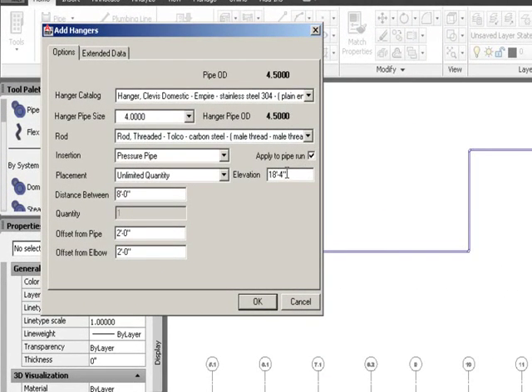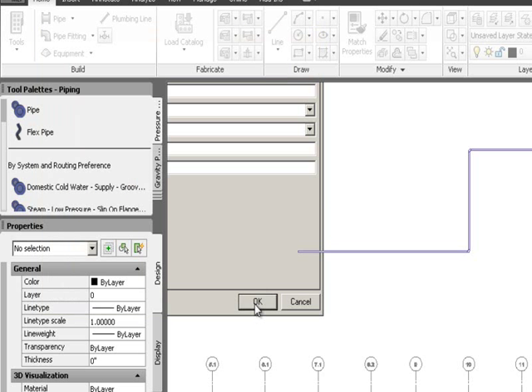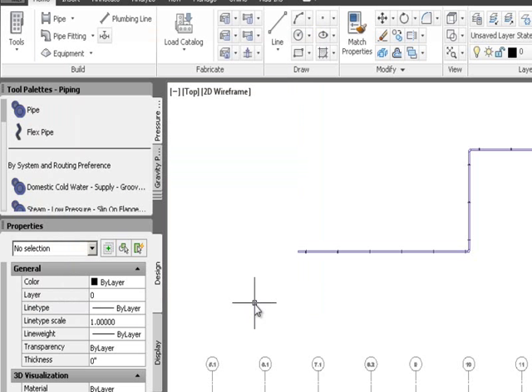I change the hanging elevation to 18 foot 4, set eight-foot spacing between hangers, and set an unlimited quantity. In the extended data tab I can specify an insert for the upper attachment and spring vibration isolation on each hanger — this data becomes schedulable and extractable from the model even though it won't model physically. I hit OK and the hangers are placed in the model.